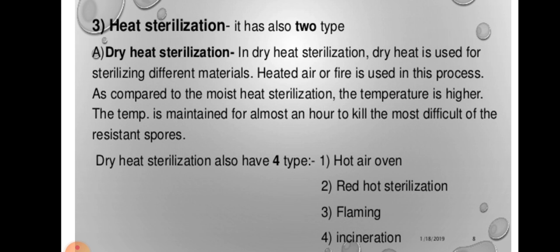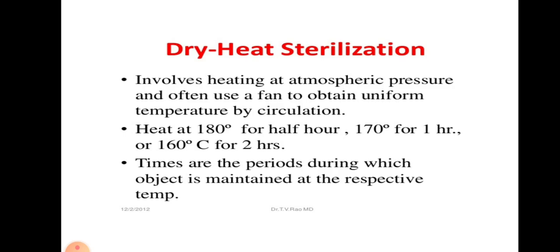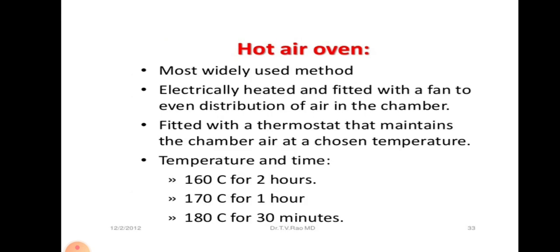The temperature is maintained for almost an hour to kill the most resistant spores. Dry heat sterilization has four types. Dry heat can be applied by four mechanisms: using hot air oven, red hot sterilization, direct flame and incineration. Dry heat sterilization involves heating at atmospheric pressure and often uses a fan to obtain uniform temperature by circulation. Heating at 180 degrees centigrade for half an hour, 170 degrees for one hour, 160 degrees centigrade for two hours. Hot air oven is the most widely used method, electrically heated and fitted with a fan for even distribution of air in the chamber.